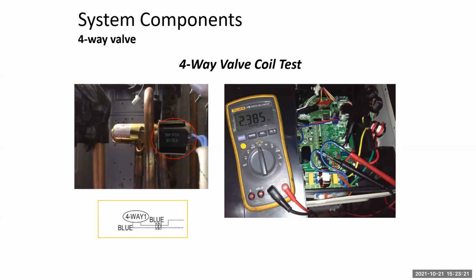Now, if you want to ohm it out, you can do that. You want to check that your resistance value is 1.8 to 2.5 kilohms on the coil. Obviously, anything to ground, you want to replace it. So just to be certain, this thing is powered up in the heating and there's no power going to it in the cooling.